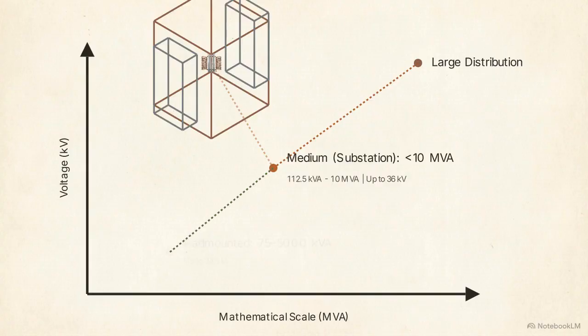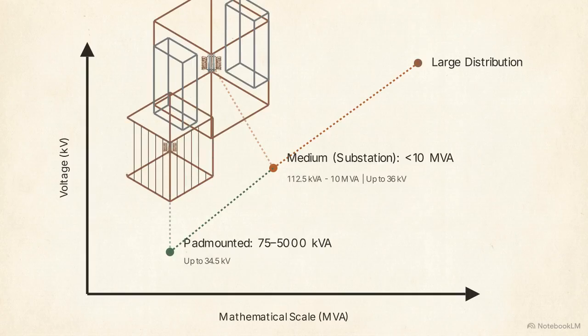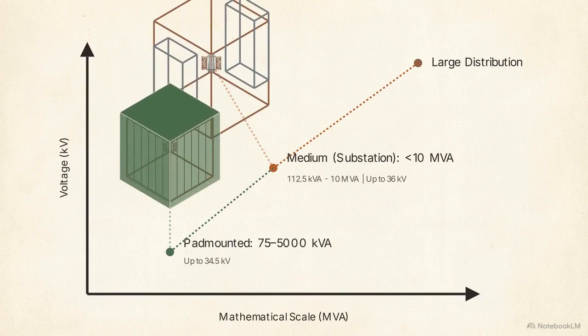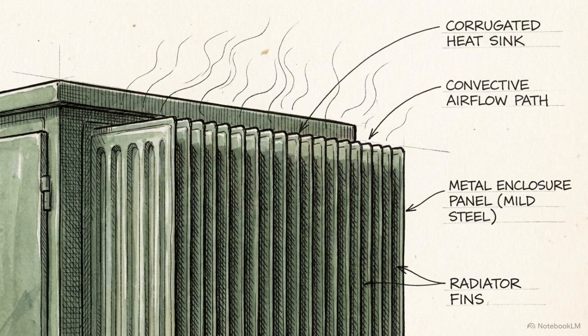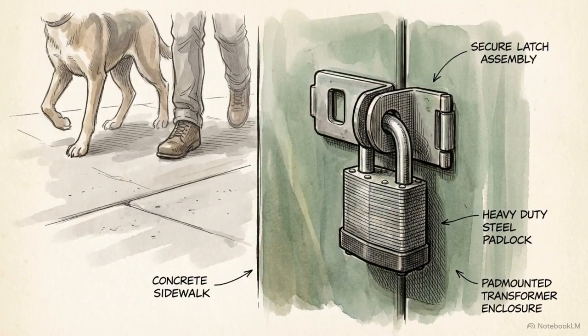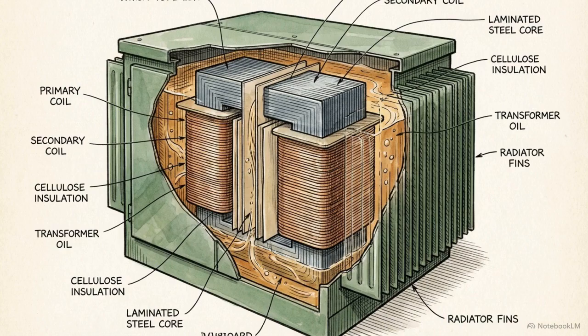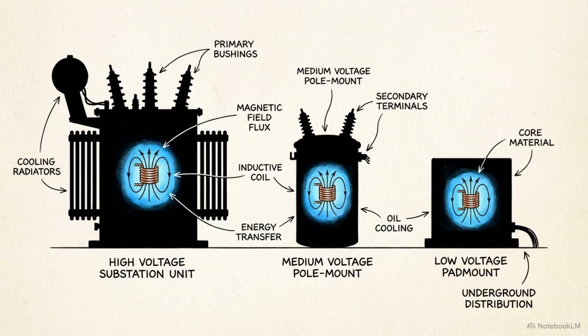Finally, at the smallest tier of the network, we find the pad-mounted class, operating directly in public-facing environments. Handling 75 to 5,000 kilovolt amperes and voltages up to 34.5 kilovolts, these units require specialized safety enclosures to isolate the active terminals. Because the thermal load is comparatively low, external radiators are entirely replaced by corrugated tank walls to dissipate heat, while the locked enclosures protect passing pedestrians. But beneath the corrugated steel and heavy safety locks, the same silicon, copper, cellulose, and oil are doing the work. The fundamental physics of induction are completely indifferent to the size, the application, or the shape of the external box.